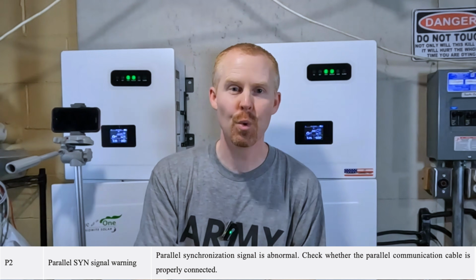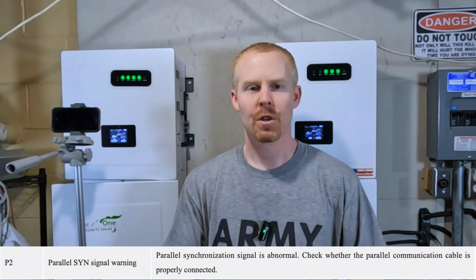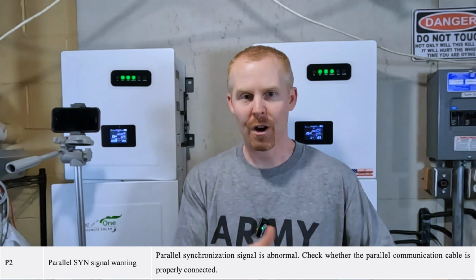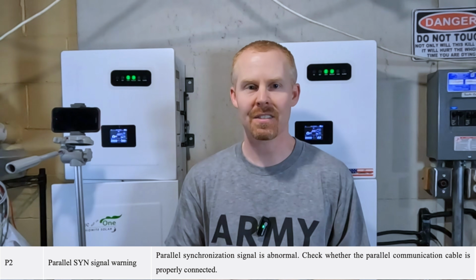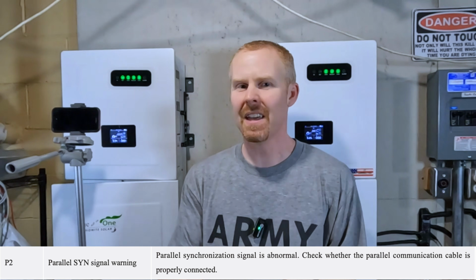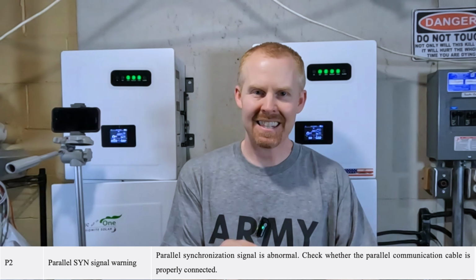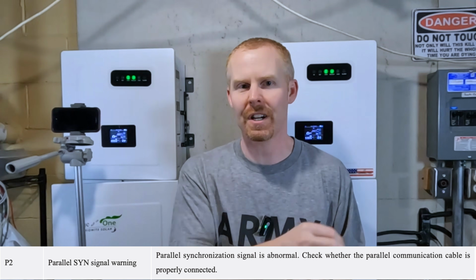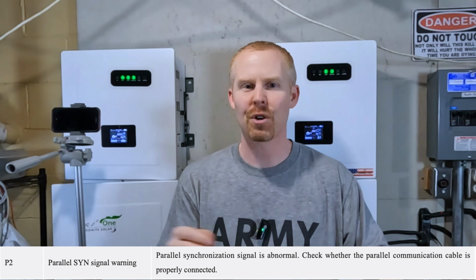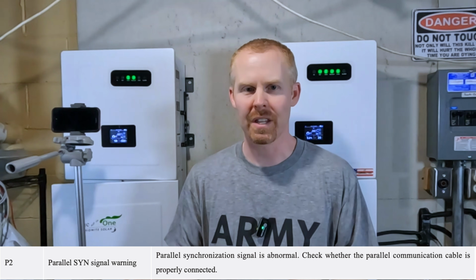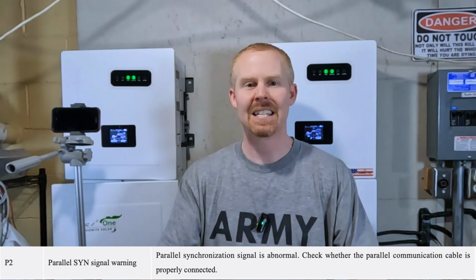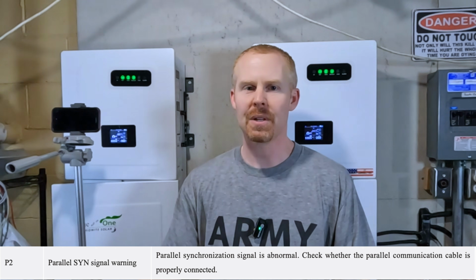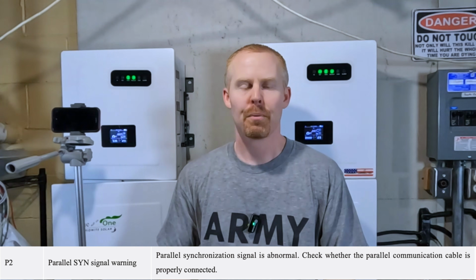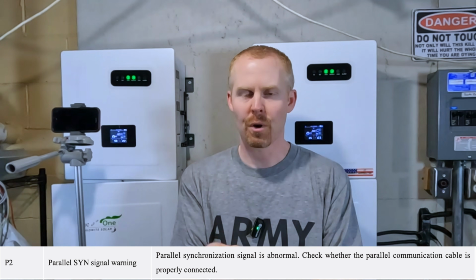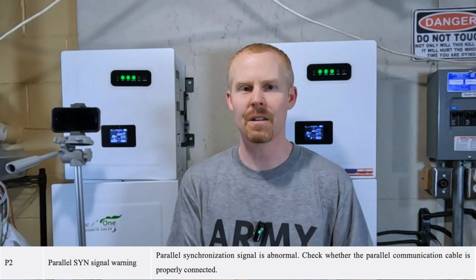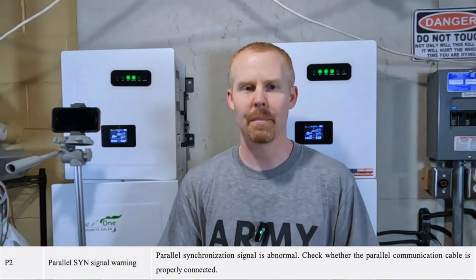If you get a P2 error, parallel sync, usually that means that parallel cable, that 4-pin Cat6 cable that we ran between the two inverters, usually that means that one pin isn't quite seated properly. So you're going to need to check those. And that's why I tone them out at the beginning so that I can make sure that everything is proper before I get through that startup procedure. And again, if you get the P2, put them both in standby, tone them out, find the wires that are not seated properly, reseat them, and then you should be able to turn it back on.